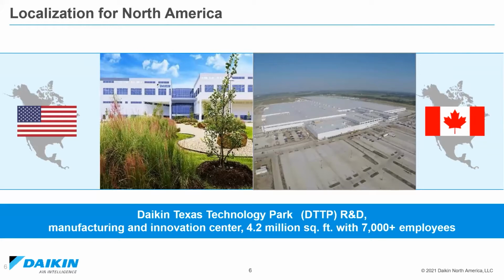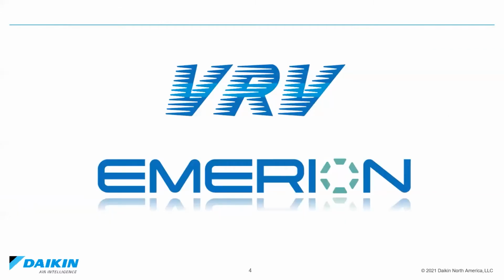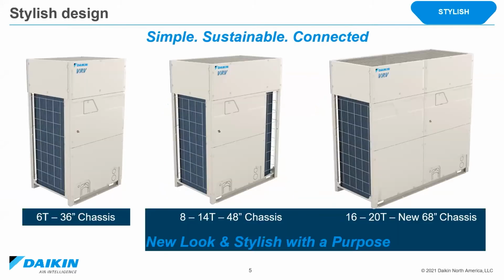Since then, over the last few years, they have had their engineers working hard on advancing VRV technology to the next level. We now bring you the Emerion line of VRV condensing units. The historic pattern of increasing capacity while reducing mechanical space is continuing with this new version. The Emerion's new design is allowing for 6 all the way up to 20 tons in a single module, and then 22 to 40 tons in a dual module. Now with the larger capacity of the single units, manifolding 3 units together is no longer needed.